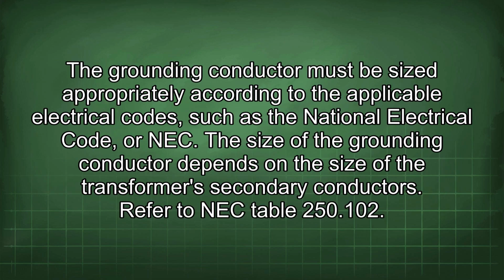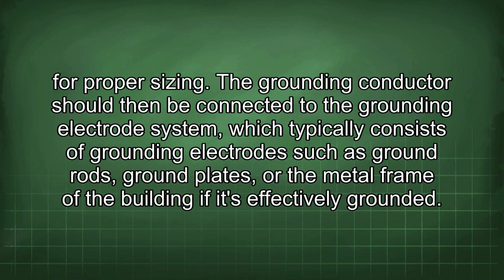The ground lug then serves as the connection point for a grounding conductor. The grounding conductor must be sized appropriately according to the applicable electrical codes, such as the National Electrical Code, or NEC. The size of the grounding conductor depends on the size of the transformer's secondary conductors. Refer to NEC Table 250.102 for proper sizing. The grounding conductor should then be connected to the grounding electrode system, which typically consists of grounding electrodes such as ground rods, ground plates, or the metal frame of the building if it's effectively grounded.